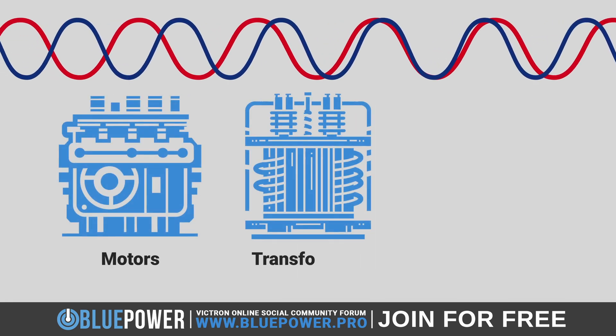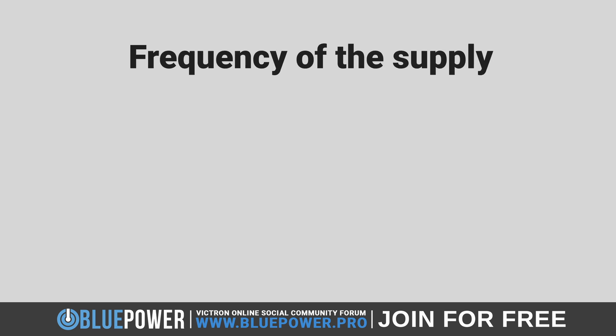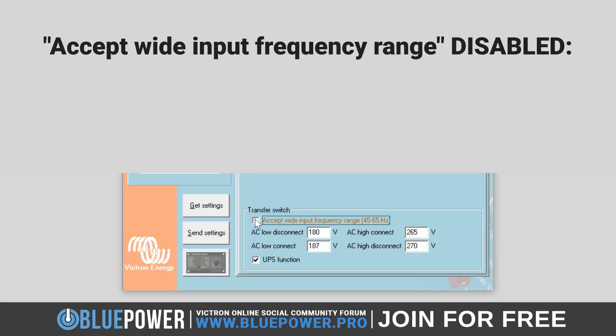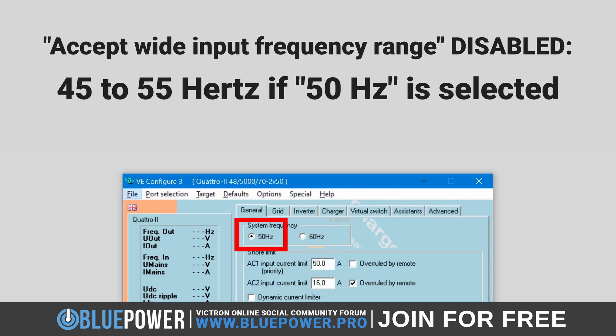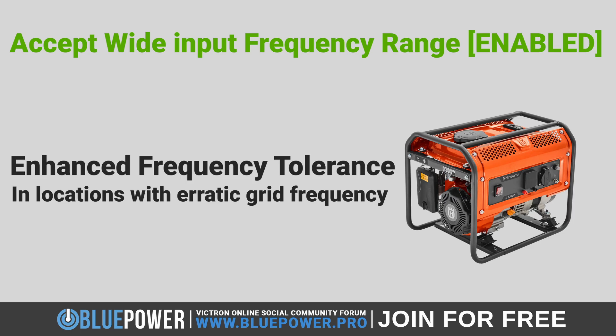This is beneficial in scenarios where the power source does not consistently maintain a standard frequency. For example, portable generators often experience frequency shifts as their engine speeds vary under different load conditions. This variability is more pronounced with conventional generators, as opposed to inverter-type models. If the Victron inverter charger is configured to only accept a narrow, standard frequency band, it might not accept power from a generator that oscillates around the ideal 50 Hz or 60 Hz frequency. In summary, this enhanced frequency tolerance is particularly advantageous in locations with erratic grid frequency or in conjunction with generators that lack frequency stability.